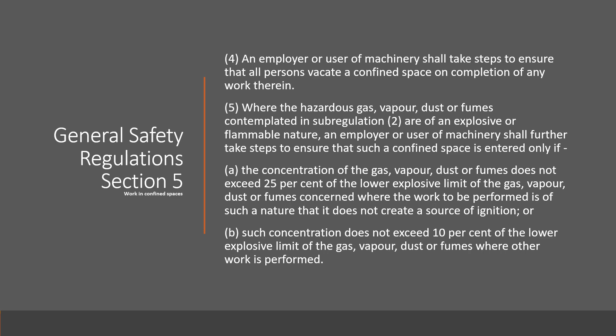is entered only if the concentration of the gas, vapor, dust, or fumes does not exceed 25% of the lower explosive limit of the gas, vapor, dust, or fumes concerned, where the work to be performed is of such a nature that it does not create a source of ignition, or such concentration does not exceed 10% of the lower explosive limit of the gas, vapor, dust, or fumes where other work is performed.